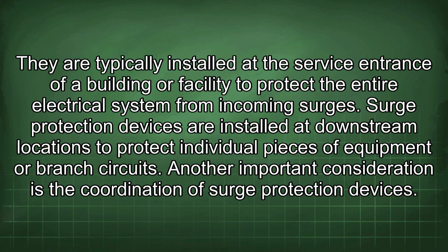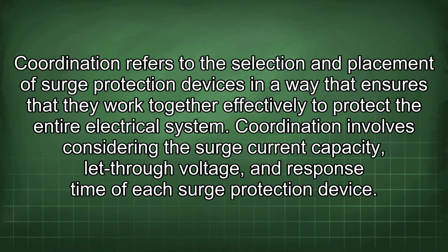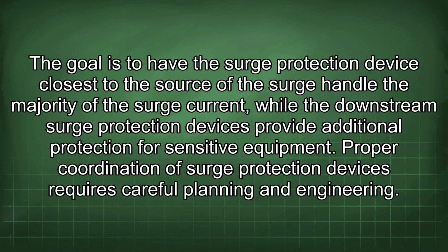Another important consideration is the coordination of surge protection devices. Coordination refers to the selection and placement of surge protection devices in a way that ensures that they work together effectively to protect the entire electrical system. Coordination involves considering the surge current capacity, let-through voltage, and response time of each surge protection device. The goal is to have the surge protection device closest to the source of the surge handle the majority of the surge current, while the downstream surge protection devices provide additional protection for sensitive equipment.